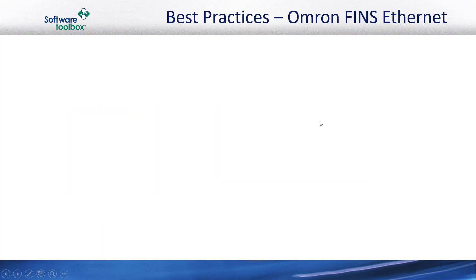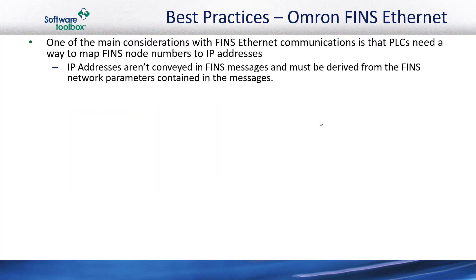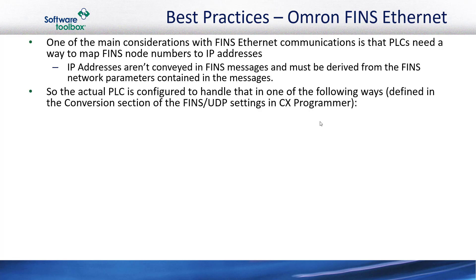I'd like to cover some best practices when it comes to the Omron FINS Ethernet protocol. One of the main configurations with FINS Ethernet communications is that the PLCs need a way to map FINS node numbers to IP addresses. The reason for that is because IP addresses aren't actually contained in FINS messages and must be derived from FINS network parameters that are included in FINS protocol messages. The actual PLC itself is configured to handle that conversion, as defined in the conversion section of the FINS UDP settings in the Omron CX Programmer programming software.